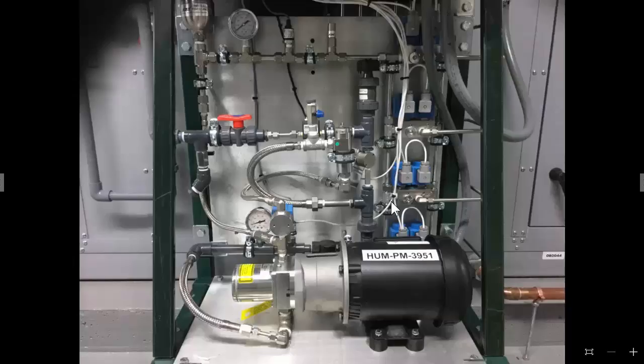But the part that is similar to the input piping, and we'll start there, is the pressure transducer, pressure transmitter that monitors the pressure within the pipe. This is the alarm point for potential problems. Like I said earlier, it monitors a low pressure if the operation of the system falls below a low pressure point, and then there's a high point where it could actually start operating at too high a pressure. Both of those will shut the system down. Like on the input water side, it will shut the system down, and it will have to be manually restarted by pushing the reset push button or the reset that's on the front of the screen.